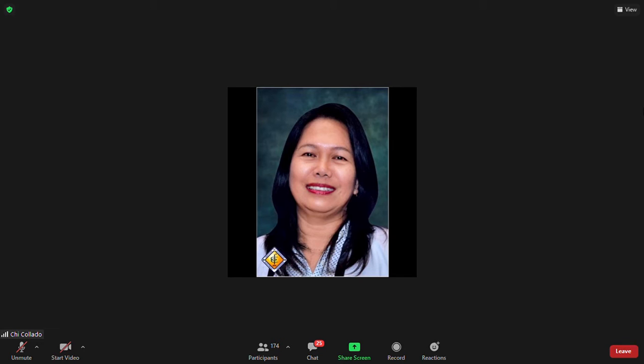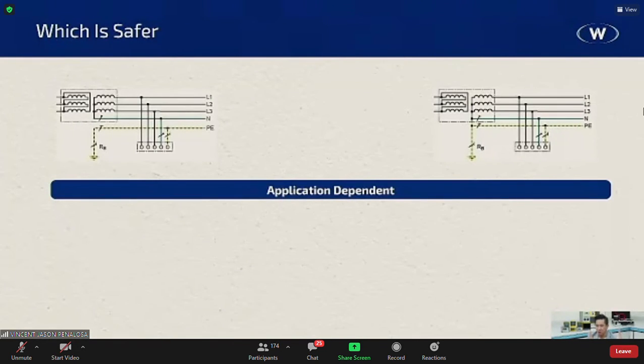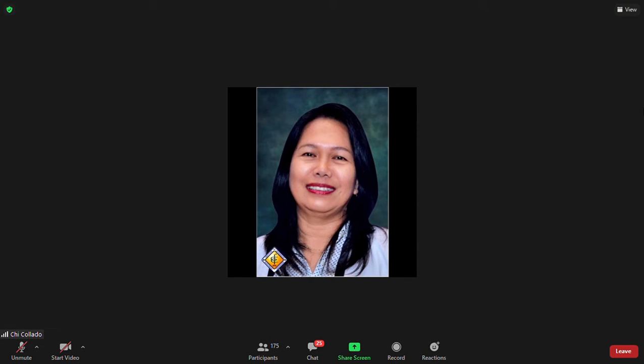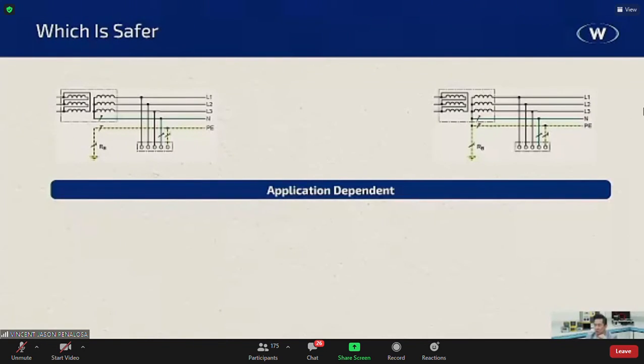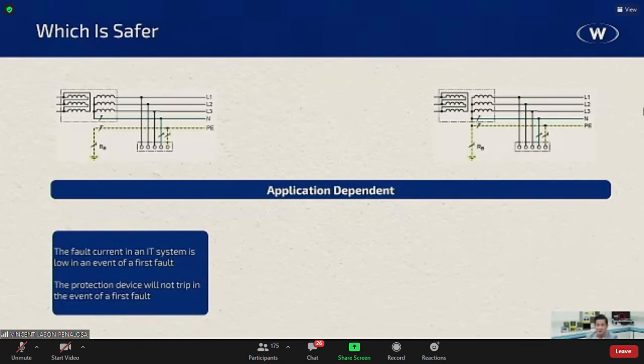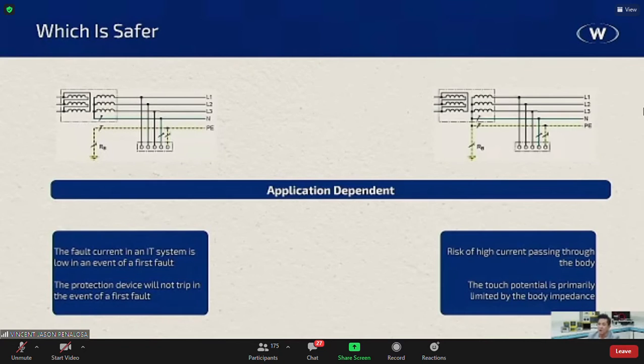So basically, for hospitals, it's not even recommended. It is in the standards that we run on an ungrounded system. So it greatly depends on the application and the design. Okay? Why did they put that on the hospitals? Why ungrounded? Because the fault current in an ungrounded system or an IT system is low in an event of a first fault. The protection device will not trip in the event of the first fault. That's why they use that on hospitals. However, in grounded system, there's a high risk of current passing through the body. The touch potential is primarily limited by the body impedance. We're usually about 400 ohms. About the regular body size, about 400 ohms.